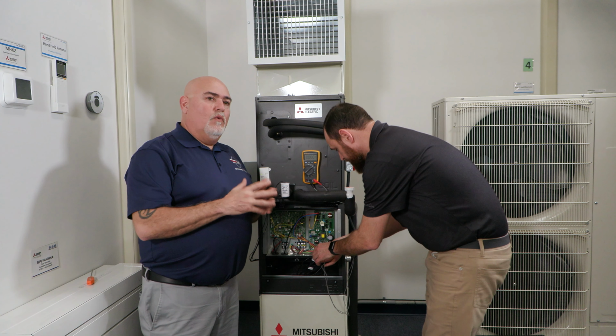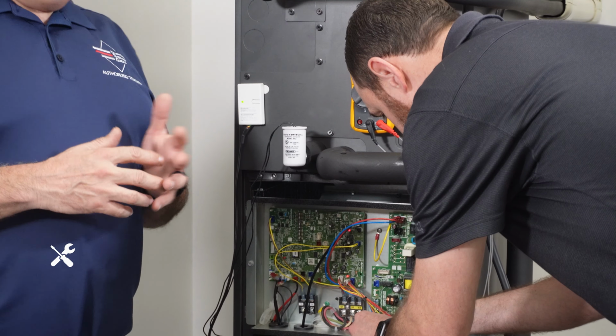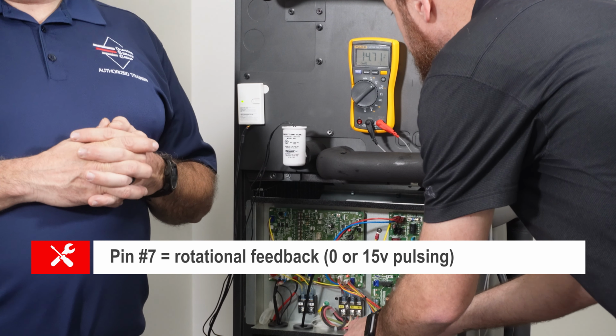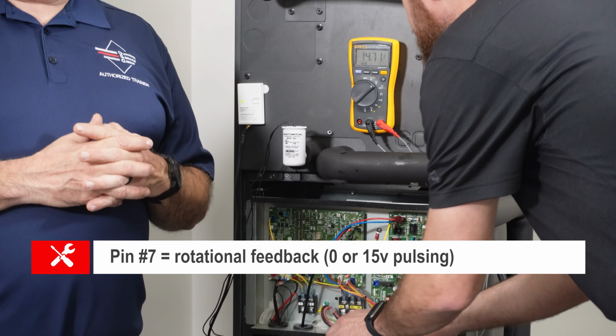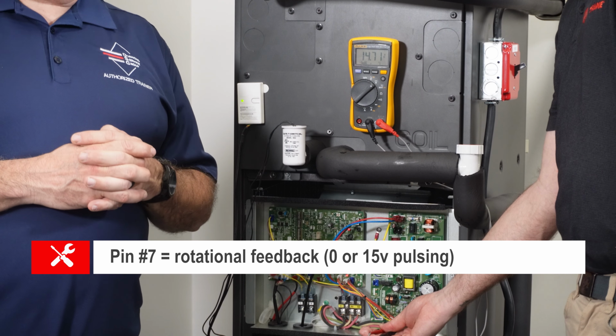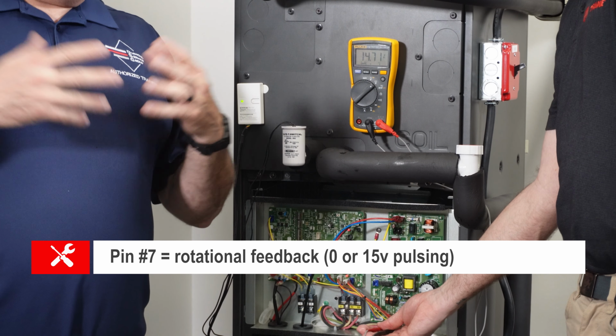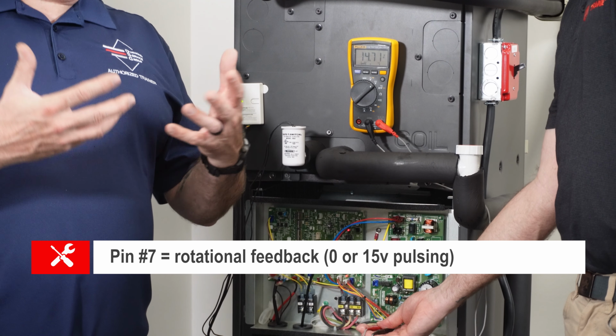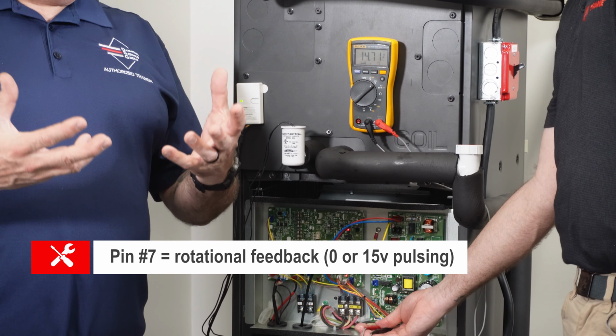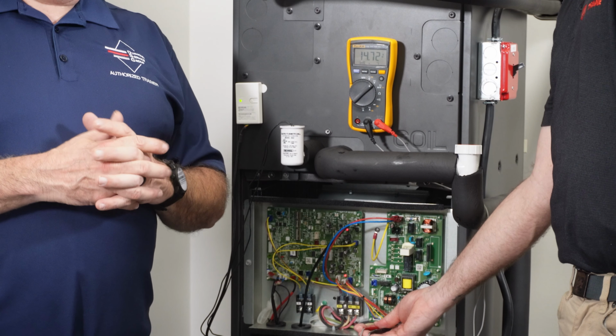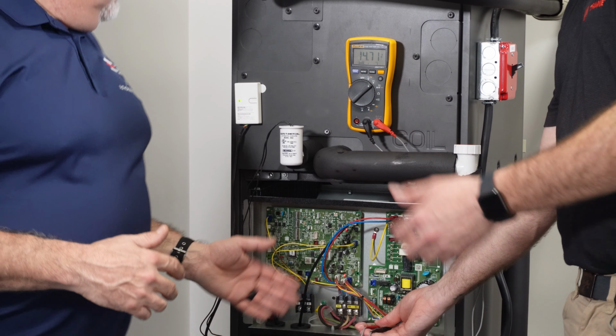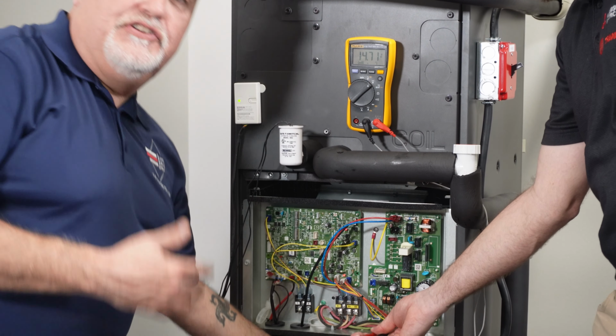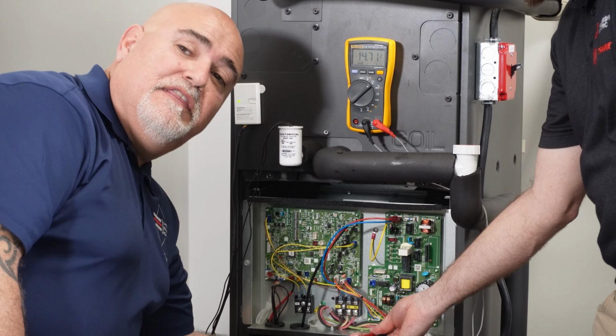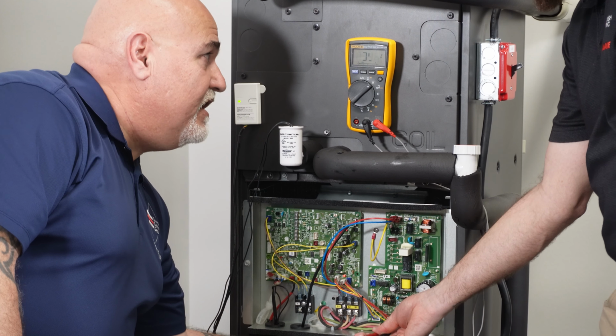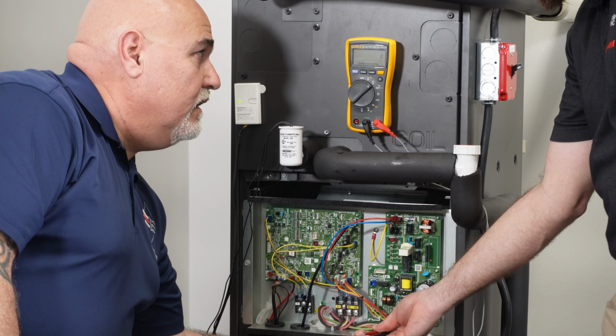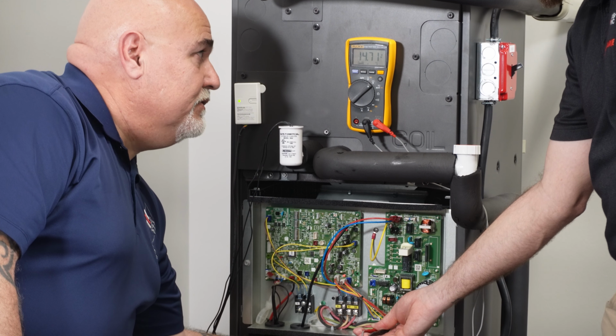Here's the critical one, the last one, and Scott's just going to jump from pin 4 to pin 7. That's our rotational feedback, and that's what throws the error code. Right now I'm reading 14.7 volts, which is the 15 volts. So how am I going to see pulsing rotational feedback, 0 or 15 volts coming back? Well, we can spin the blower wheel by hand. Make sure your system's off before you stick your hand in there. We're going to spin that squirrel cage blower, and you can see on the meter that it is pulsing from 0 to 15 volts.